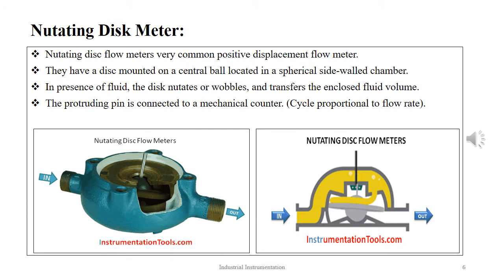The first type of positive displacement flow meter is the nutating disc meter. Nutating disc flow meters are very common positive displacement flow meters. They have a disc mounted on a central ball located in a spherical sidewall chamber. In presence of fluid, the disc nutates or wobbles and transfers the enclosed fluid volume.